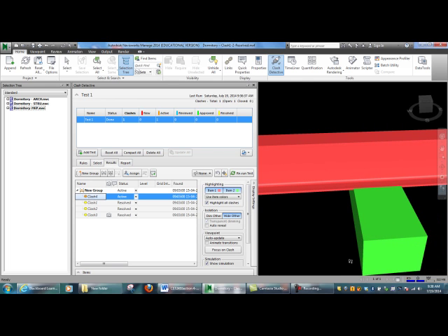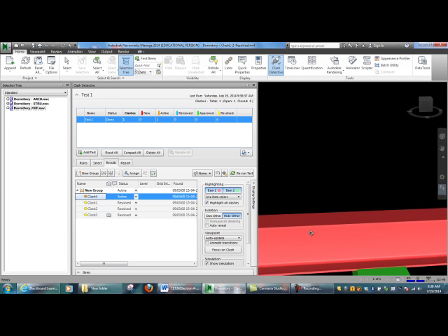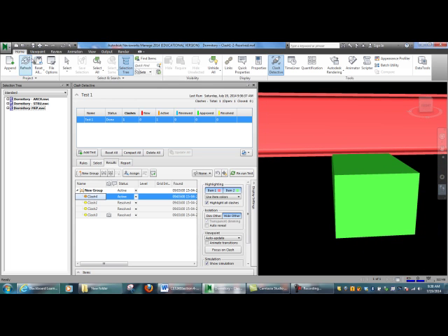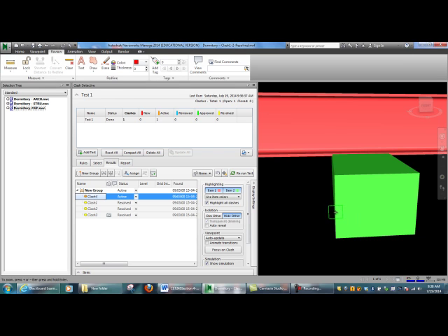One of the things that it asks you to do is to measure the duct roughly to see what it looks like, or how big it is. Okay, so if you go to review, there's a measuring tool, and this can be approximate. It's not going to be perfect. It's about 9 and 3/16. That's probably a 10-inch duct. You can go up here, click on the top, and click on the bottom. It says 7 3/4, so that's probably 8 inches deep.